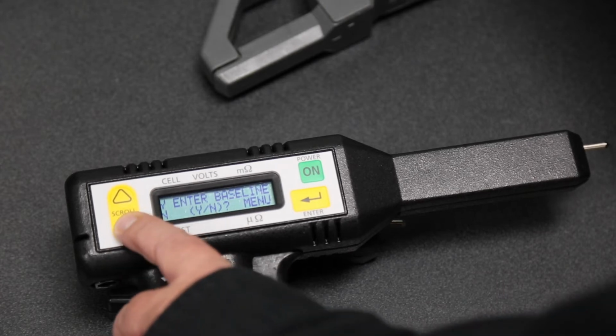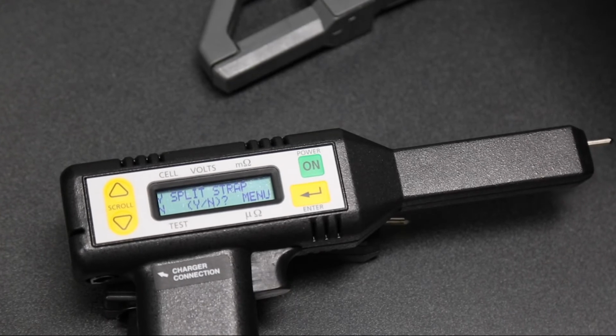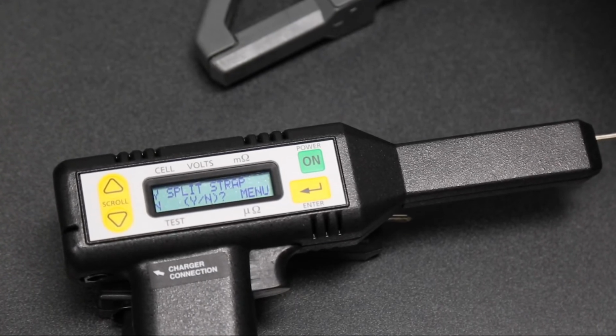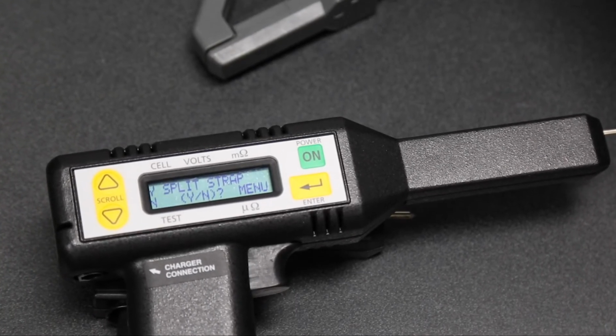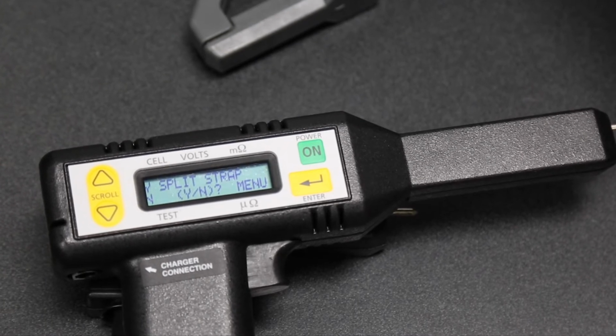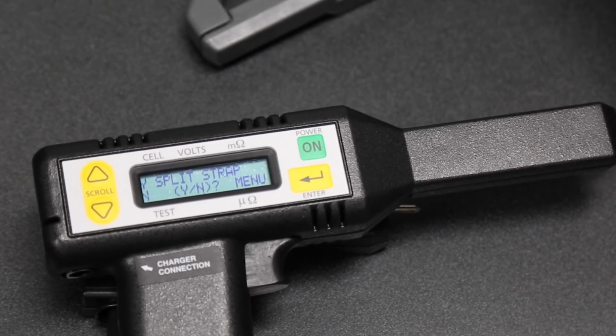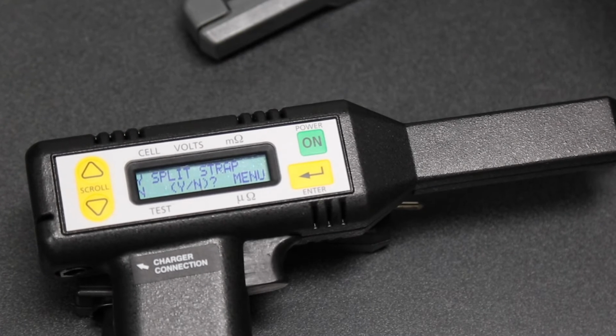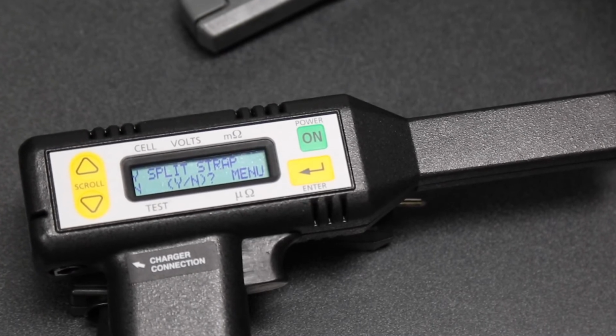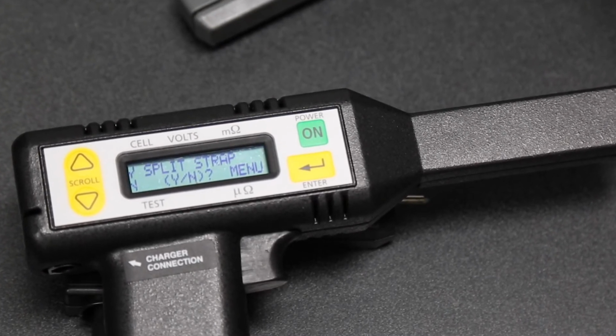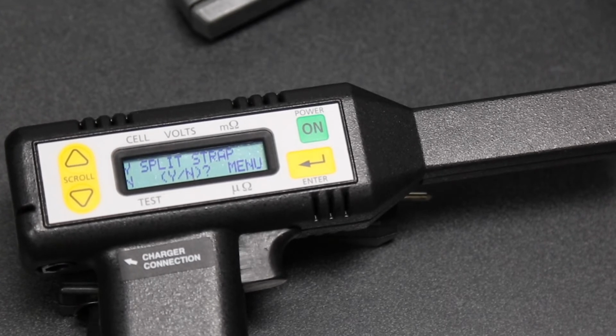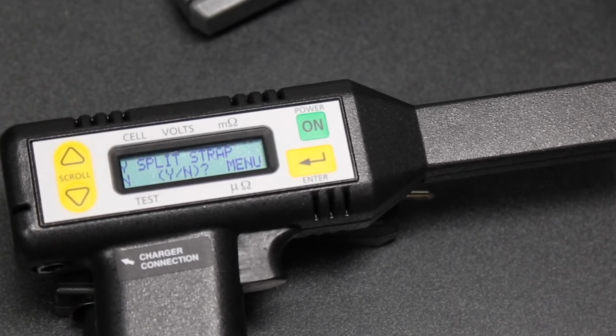I can now select a split strap. This is applicable to high current strings. The receiver uses a CT to measure the test current going through the string. If you have parallel straps in your string that the test current can be split, then this setting puts a multiplier in the receiver to compensate for this. The string I'm testing only has one path for current, so I will select No.